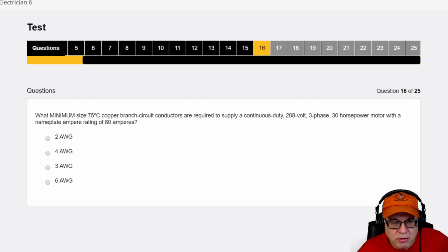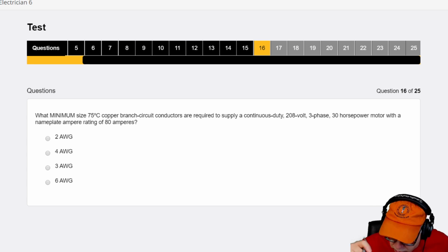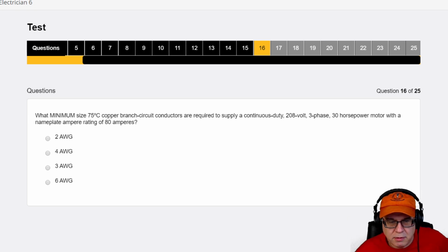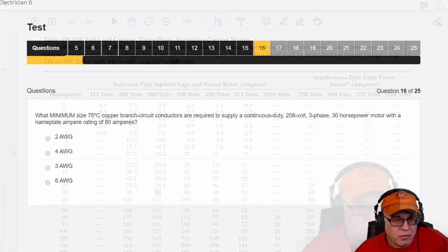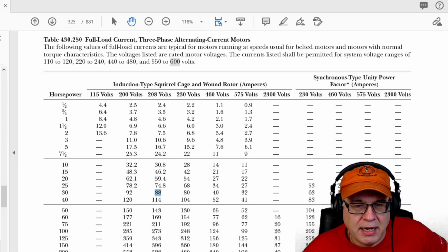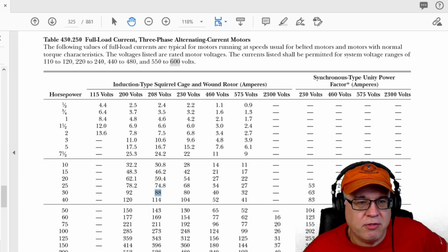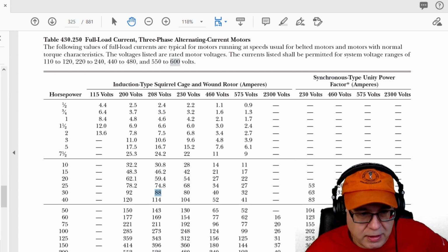So it's 30 horsepower, 208 volts, 3-phase. That gives 88 amps. I'm going to write that down real quick on my cheat sheet, the paper they give you at the exam - boom, boom, boom. There's the 88 right there, from Table 430.250, 3-phase, 30 horsepower... 88. So that's our amps.